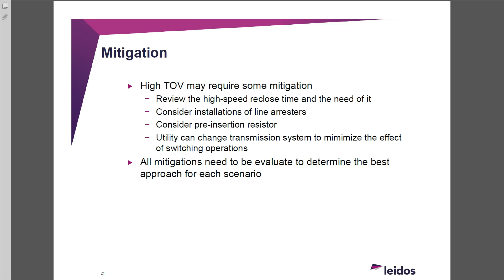Wait, so at one per unit you open, then they'll have the overvoltage, and if for some reason they open during that overvoltage, it's going to be even higher, right? Because it's already there, so it accumulates—if you close again, you're going to have a worse overvoltage. Exactly, very interesting.